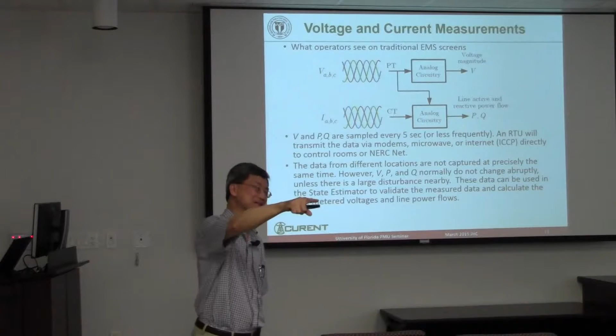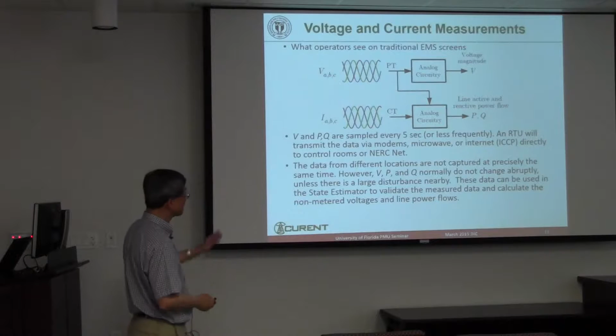Power system engineers are pretty clever. How can you do this? Because voltage, P and Q don't change abruptly. Their values may be slightly different from earlier, but they don't really change 50%. As a result, you can do state estimation. The premise of the state estimator is that every measurement has the true value plus some uncertainty, due to the measurement itself or the time difference. This works very well.